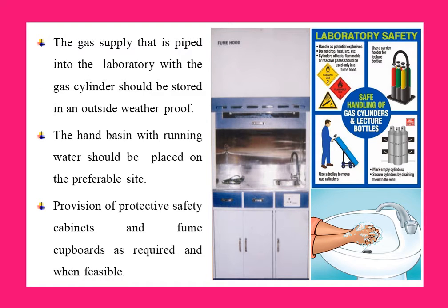Next, the gas supply should be piped into the laboratory, with the gas cylinder stored outside. So we should always store the gas cylinder in a weatherproof outside jacketed cover, so that any other gas cylinder, if it comes in contact with it, should not react and should not catch fire.